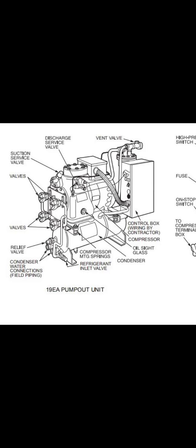Then after that, when the liquid is pushed out, remove the vapor. So reverse the cycle, and how do you remove vapor? You go to vapor, take the suction line from the system, go into the pump out unit, and the pump out unit discharges through its own condenser, converts it into liquid and transfers it to the storage tank. I think maybe this will help somebody understand, because this is a very big plant and big refrigerant charge, so we are doing it like this.